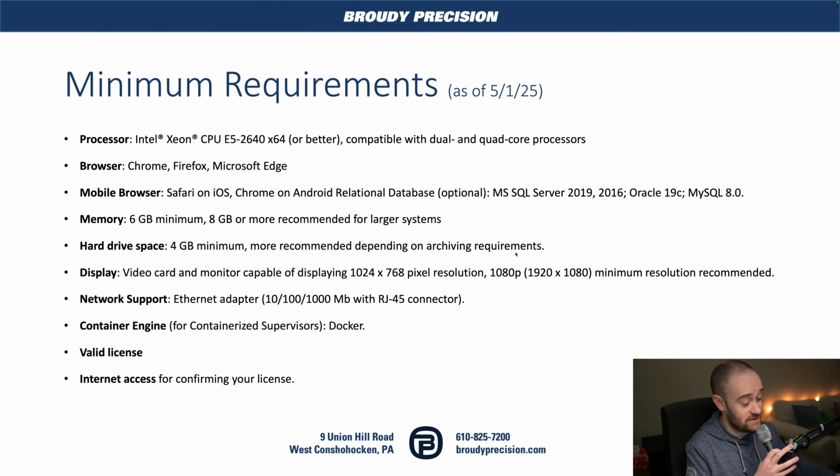All right, so minimum requirements. Niagara is a super light application by default by itself. It doesn't require much. So you'll see here what looks a little intimidating on the processor side of things. It's calling for a Xeon processor. This Xeon processor was released in 2012. So pretty much any modern day processor, new processor, will be totally fine for running Niagara. You'll see that the basics, it wants dual or quad core processors. Nowadays, it is not uncommon to see an 8-core, 12-core, 16-core processor, even on the lower end of things. So nothing to worry about on the processor side.